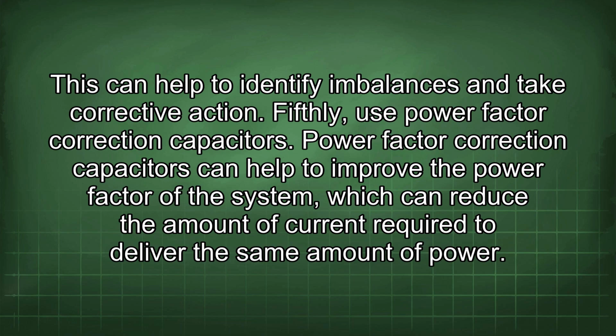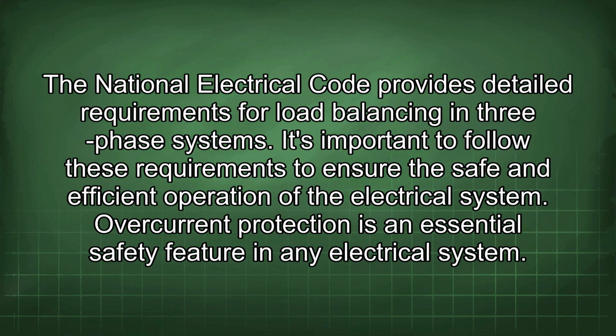Fifthly, use power factor correction capacitors. Power factor correction capacitors can help to improve the power factor of the system, which can reduce the amount of current required to deliver the same amount of power. The National Electrical Code provides detailed requirements for load balancing in three-phase systems. It's important to follow these requirements to ensure the safe and efficient operation of the electrical system.